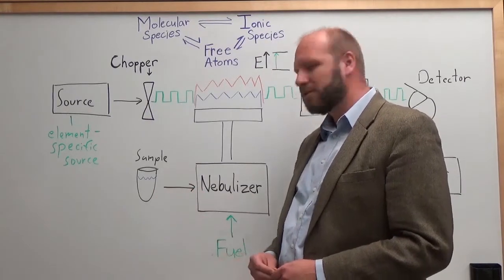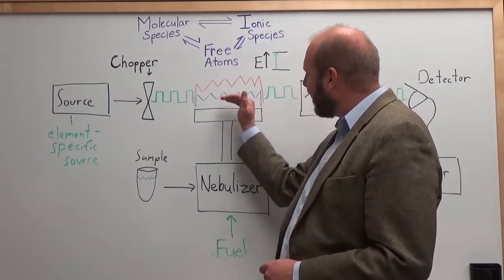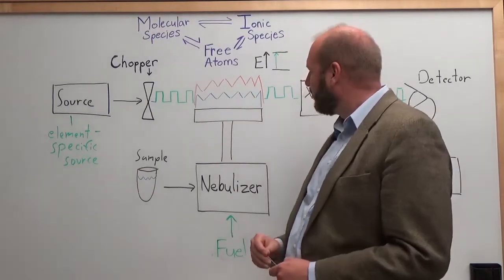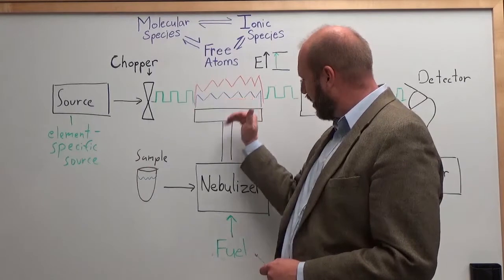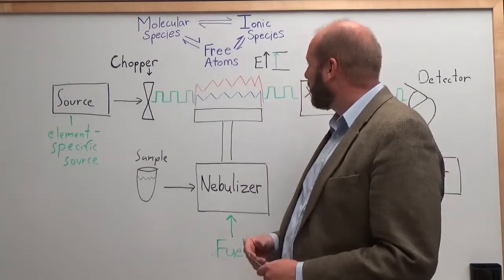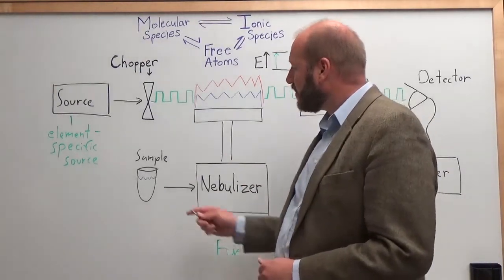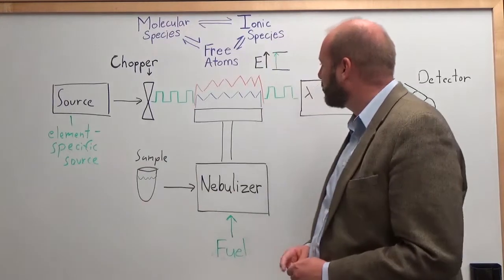The nebulizer takes our liquid samples and turns it into an aerosol. We mix it with fuel and bring that up into our flame. In the flame, we have a combustion area where organic species can be burned off and we can create our free atoms. Our free atoms can then absorb our wavelength of interest from our element-specific source.